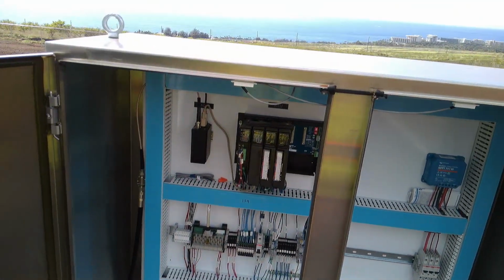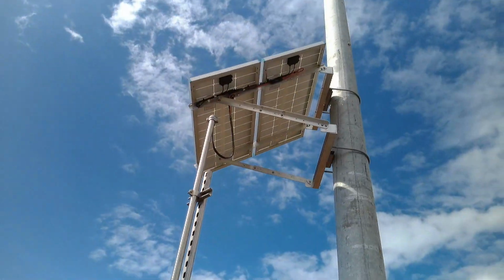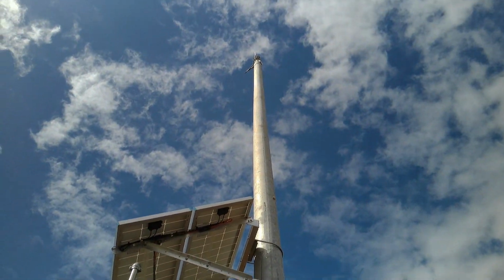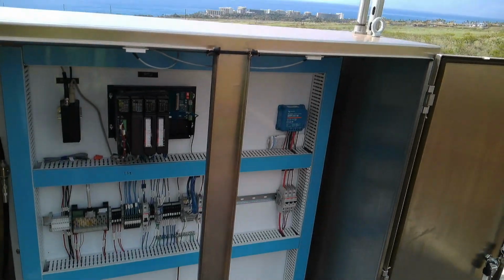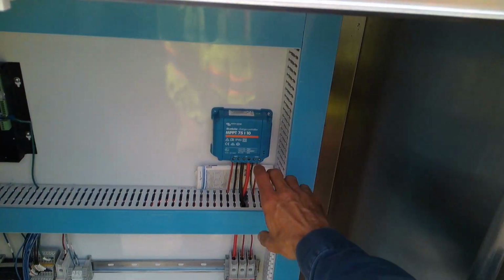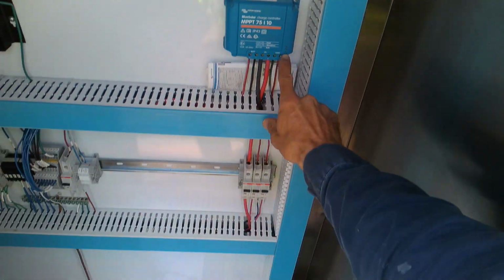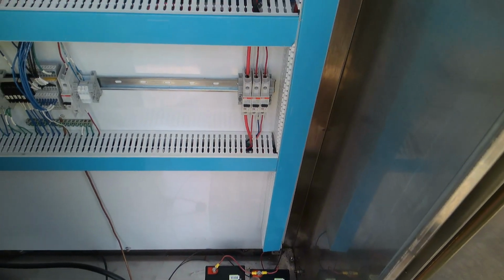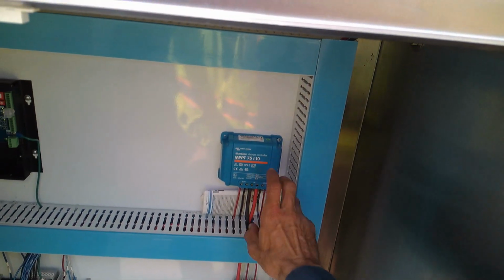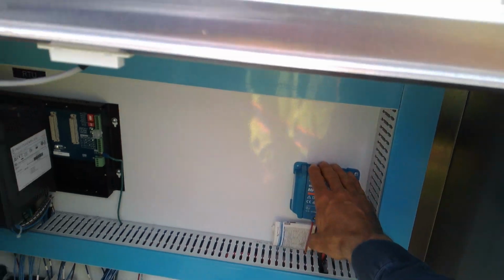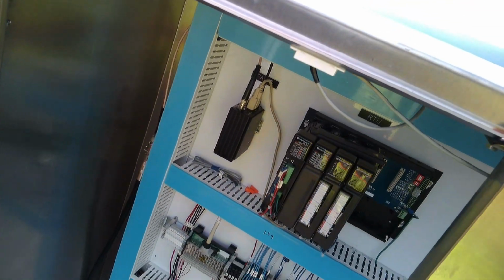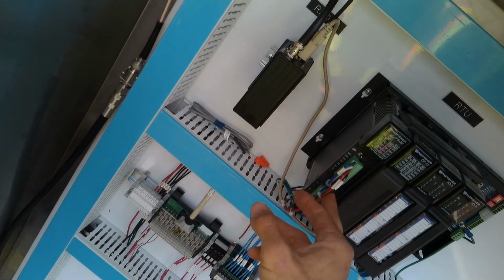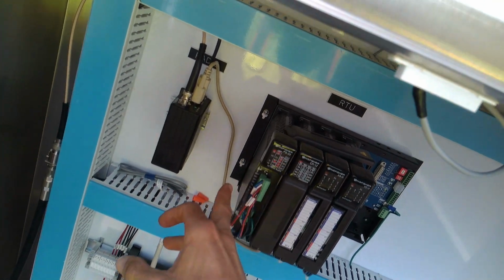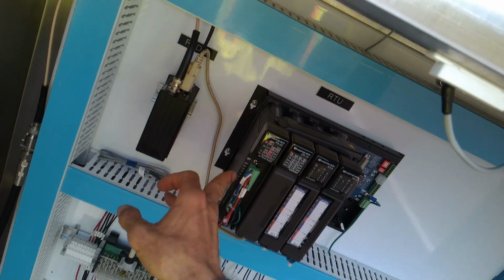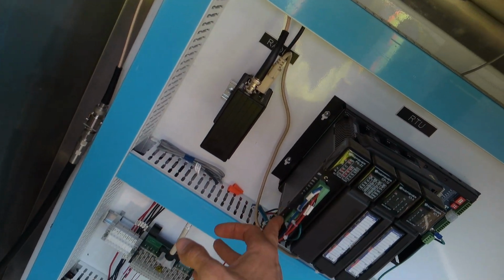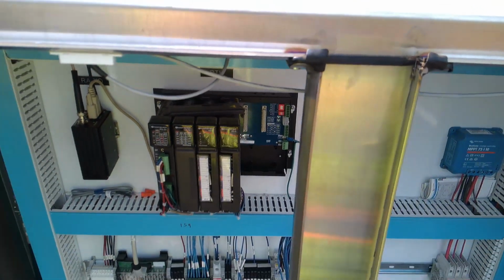Here's our tank control panel. Solar panel, antenna. And here's this blue solar charge controller from Victron Energy. So right now we've got them wired up in parallel, 12 volts DC. This guy's working, everything's happy, but we want to run them in 24 volts DC. We've got this Kingfisher RTU temporarily wired into its backup battery ports, which take 12 volts, but we want to use its primary power source of 24.